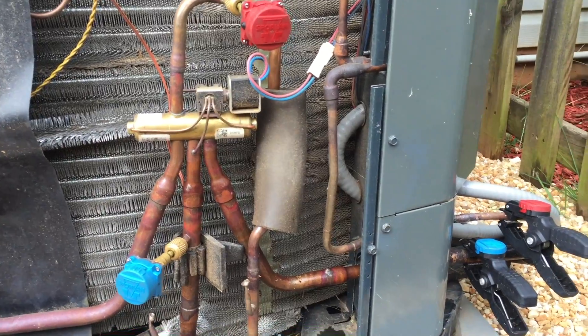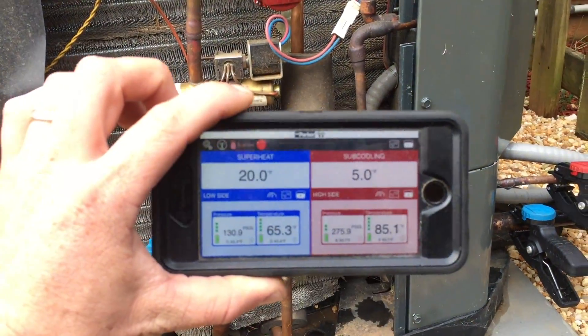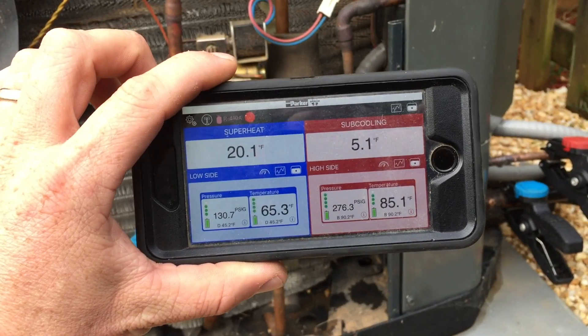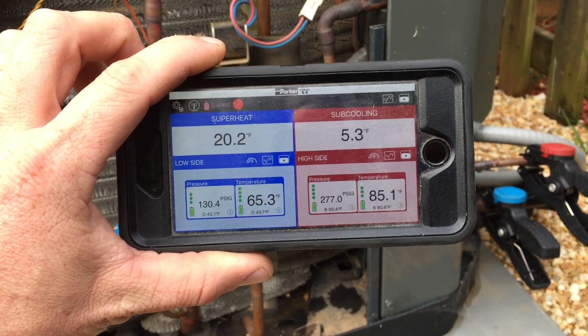Right now I've got the Sporlan Smart Service Tool connected to the system. We've got 5 degrees of subcooling and 20 degrees of superheat.